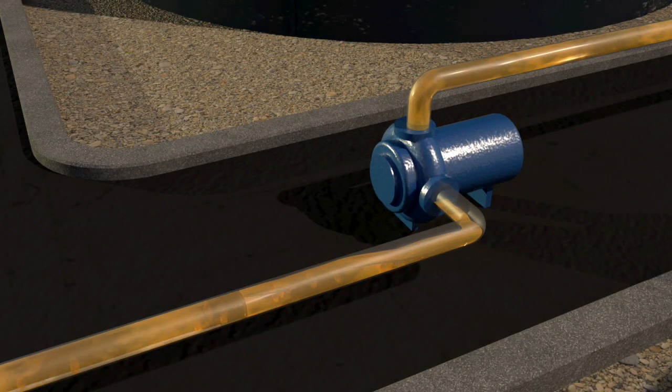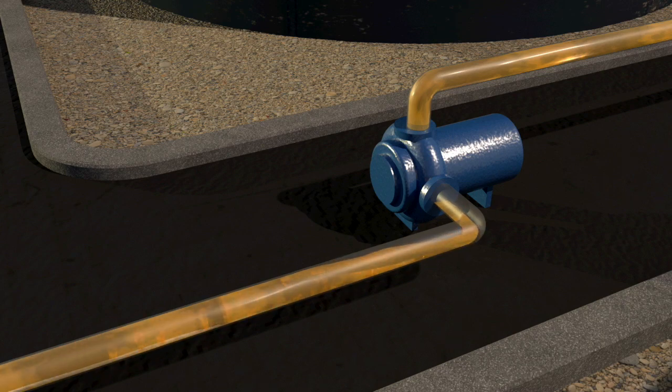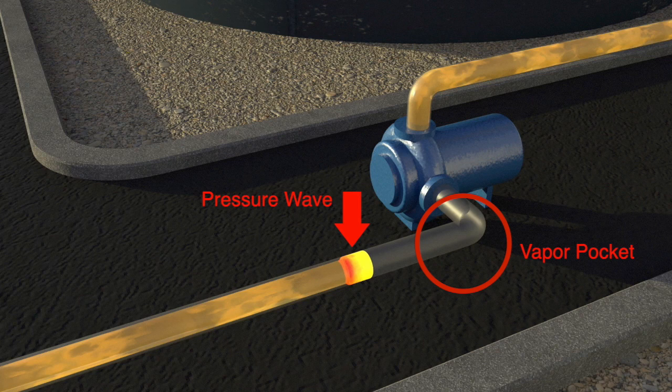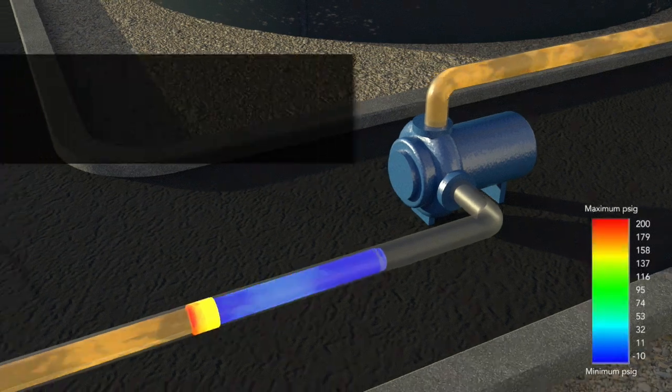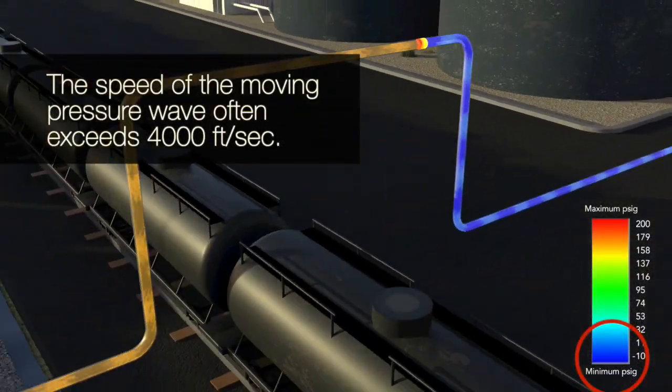In a low-pressure surge event, vapor pockets can quickly form as the pressure wave is emitted out. The speed of the moving pressure wave is a function of elasticity of the fluid and pipe, often exceeding 4000 feet per second.